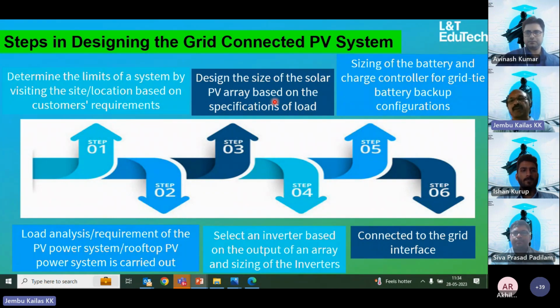Suppose you are going to produce 50 megawatts of power, then you have to go for a 220 kV level system; you cannot synchronize with a normal 11 kV system. We have to do a good study for grid connection. If you're only producing 1 kilowatt, there's no problem, you can connect directly to an 11 kV line or 415 line. But if it's more than that, say 10 megawatts, you should discuss with the EB, and accordingly select the inverter.